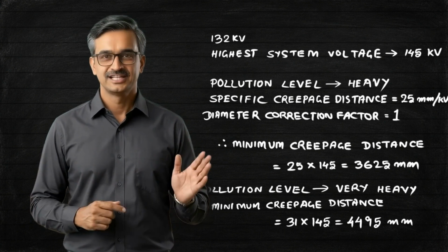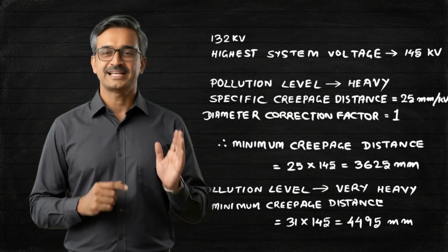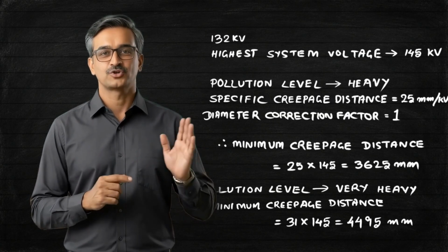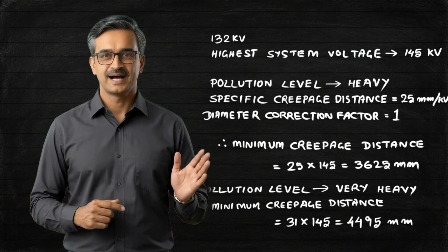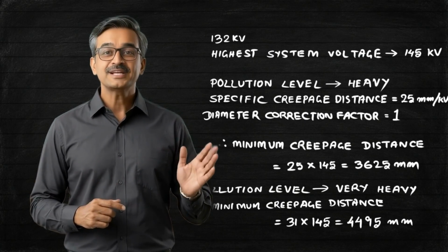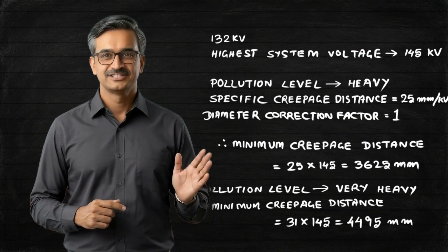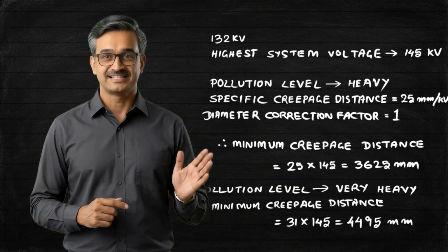Important design considerations. While selecting an insulator, don't look only at the creepage distance. IEC also recommends considering several profile parameters including shed spacing, shed inclination, average diameter, and the mounting position of the insulator. These factors influence the pollution performance of the insulator.